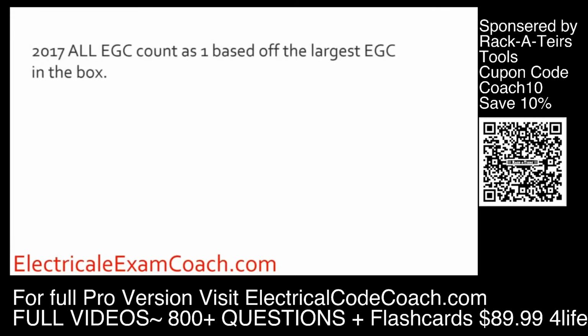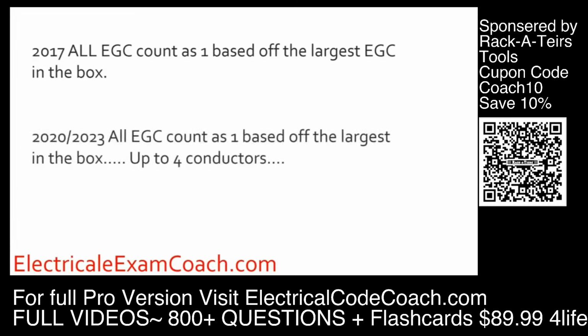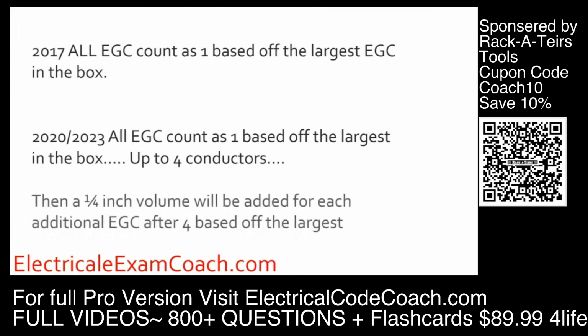Now let's deal with equipment grounding conductors. In the 2017, all equipment grounding conductors just count as 1 based off the largest conductor in the box. 2020 and later, all equipment grounding conductors count as 1 based off the largest conductor in the box up to 4 conductors. So 4 conductors and under count as 1 total. But when you have over 4, there's going to be a 1/4 inch volume increase added for each additional equipment grounding conductor after 4. I'm going to teach you how to do it one step at a time.